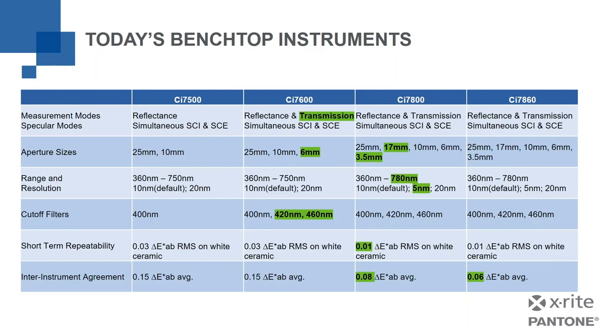Now, initially, the difference from 0.08 to 0.06 might not seem significant, but if you're producing something, and we have customers in this situation where your tolerance is 0.25 or 0.3 delta E, the less of that tolerance that you consume with the variation between instruments, the better. So 0.06 makes a big difference in that case.